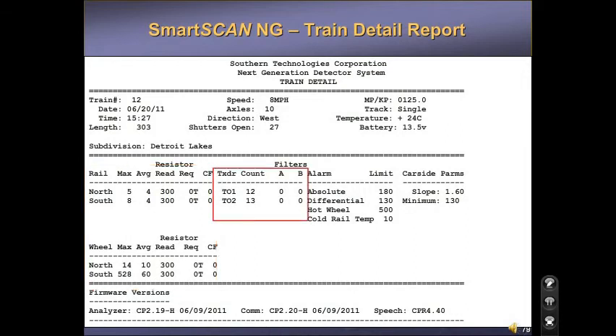This section of the reports shows the TO1 and TO2 transducer counts. This information is the same as the summary report. The filter columns refer to performance issues of the transducers. Filter A refers to the pulse width filter, which is set at 3 milliseconds. Any pulses on the transducer less than 3 milliseconds will be filtered out, and the counter will be incremented. Filter B refers to the timing between transducer pulses and is set for 300 milliseconds. This means if a pulse is received and then a second pulse is received in less than 300 milliseconds, the second pulse will be filtered and the counter incremented.